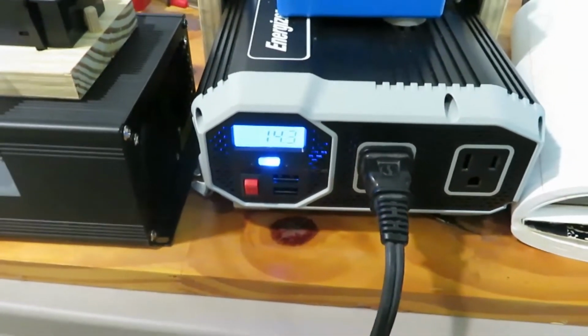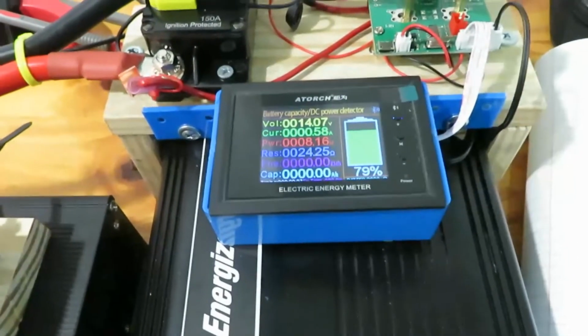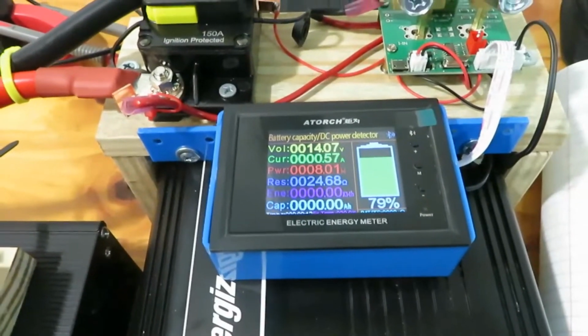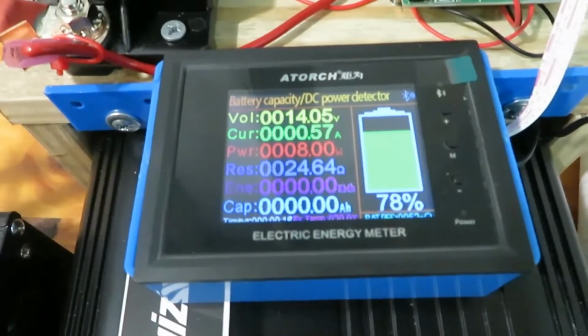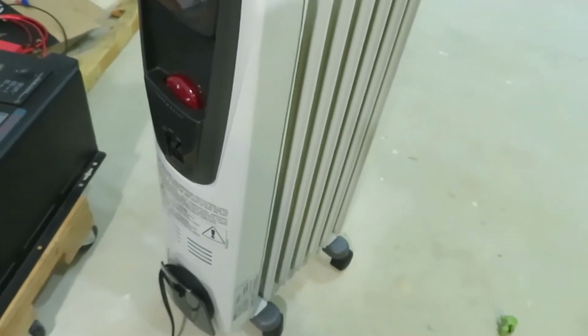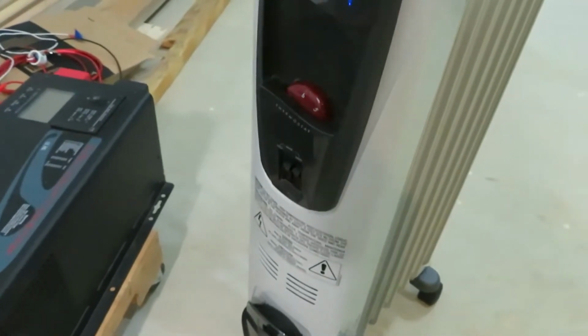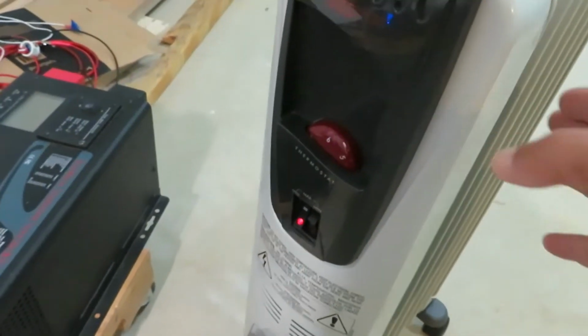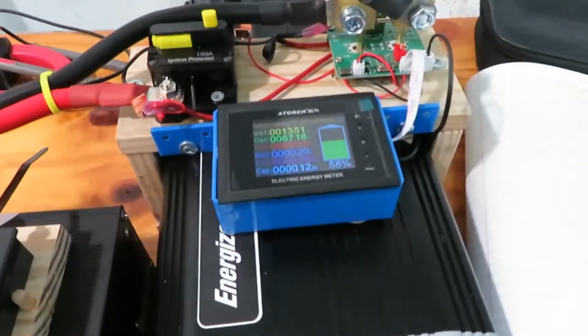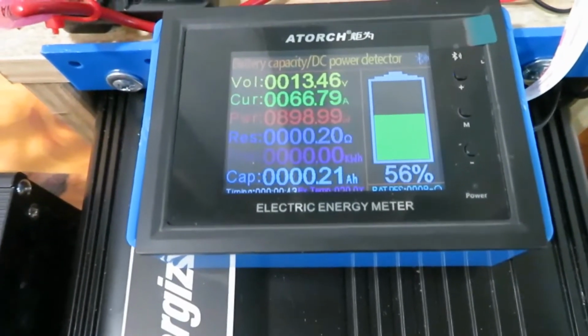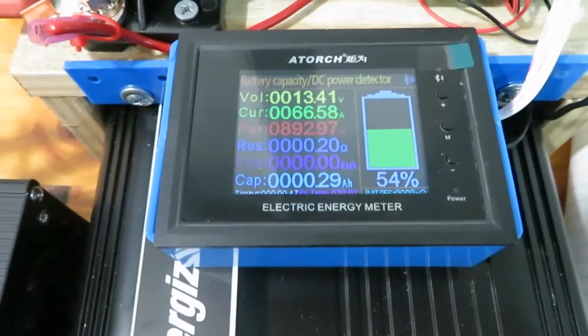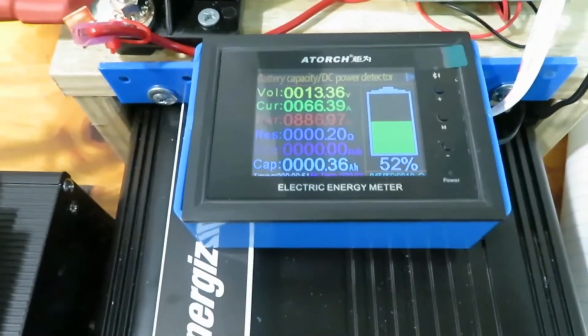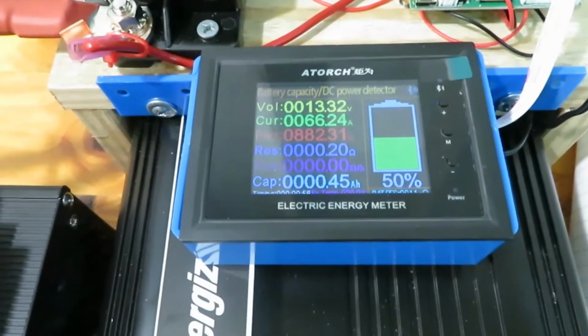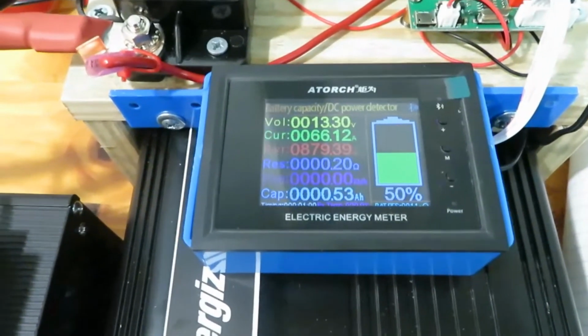So let's turn on the inverter. Okay, the inverter is on right now. And the inverter itself is drawing 0.58 amps. So that is the overhead of the inverter. 0.57 amps. And the load we have is a heater. This heater is about 1500 watts, but I'm going to just use half of that. So I just use half the heater. I turn on the heater. Now the heater is going, and right now it's drawing 66.7, about 67 amps. So now the power is about 885 watts for the heater and the inverter combined.